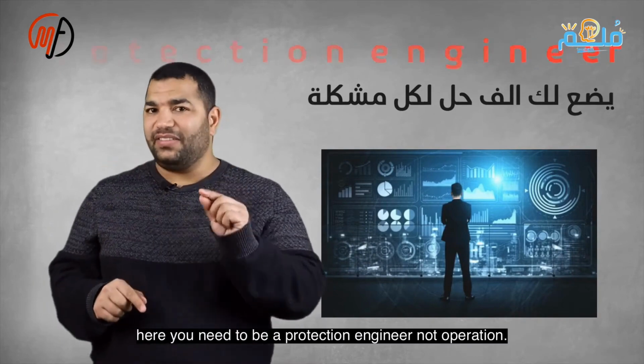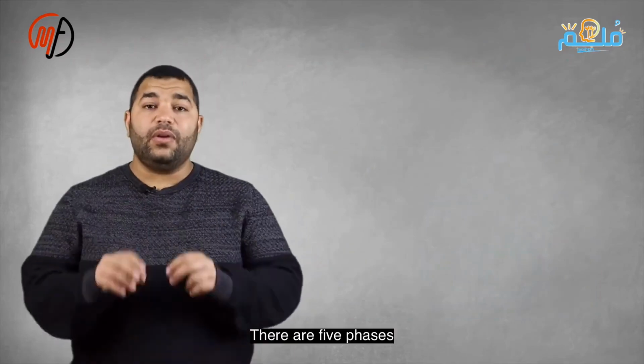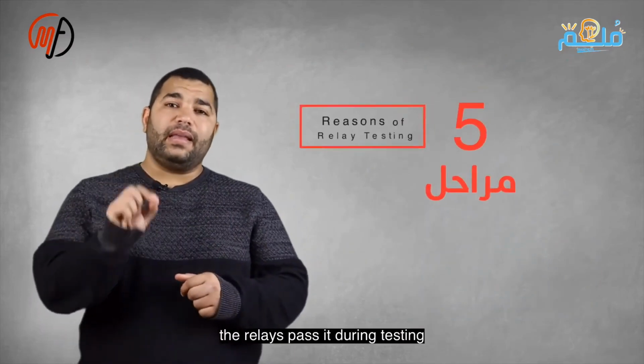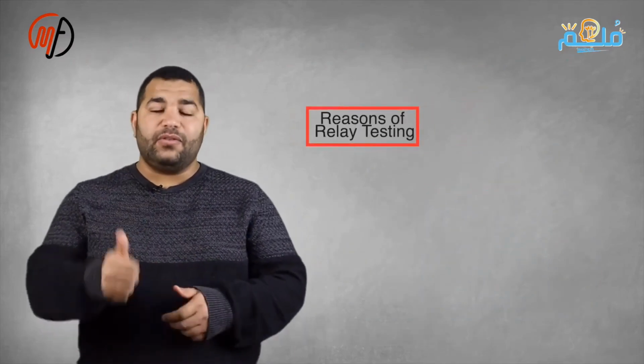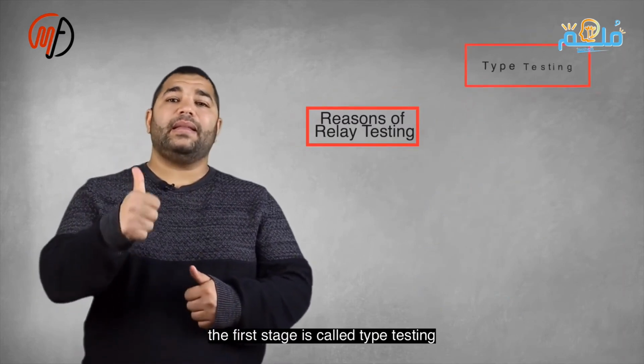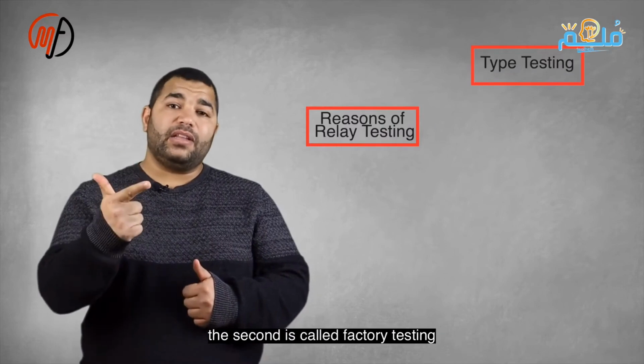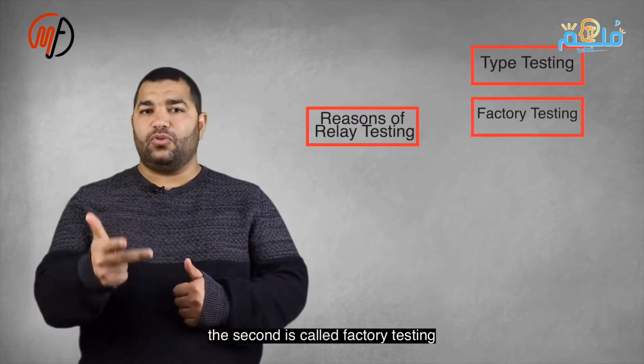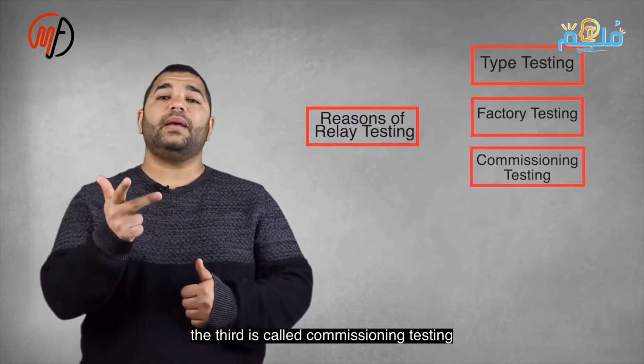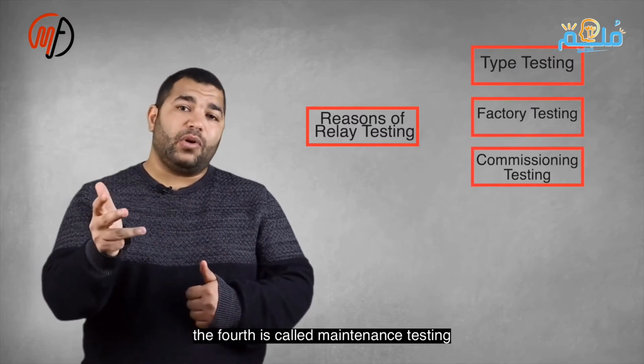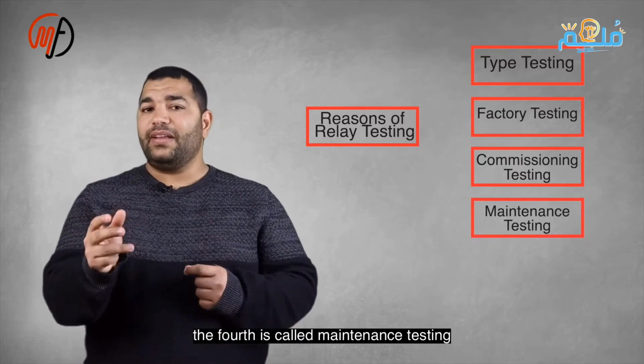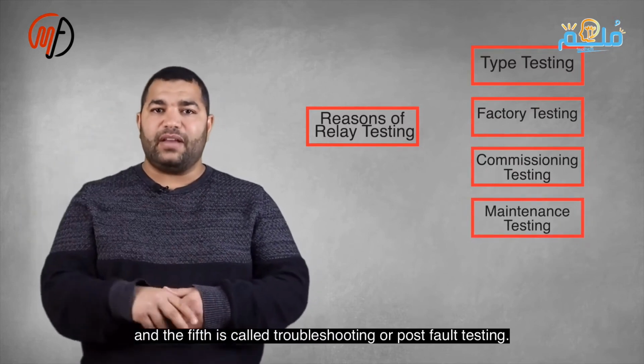The first stage, the second stage, the third stage, the fourth stage, in addition to the first stage, which is type testing. It is a test conducted by the manufacturer to prove that this new relay is capable of entering the market strongly and can detect all faults. This proof is for the end user, whether it's electricity companies or any other private companies.